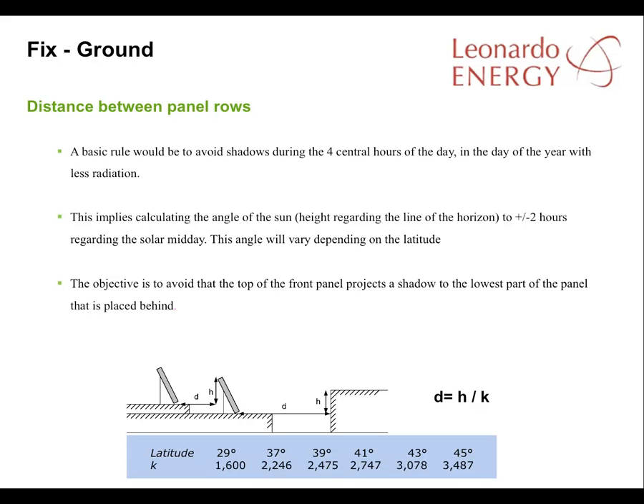That means calculating the height of the sun above the horizon to plus or minus two hours at solar midday. The angle will vary depending on the plant's latitude. The objective is to avoid a situation where the tops of the front solar panels project a shadow onto the lowest parts of the panels placed behind.